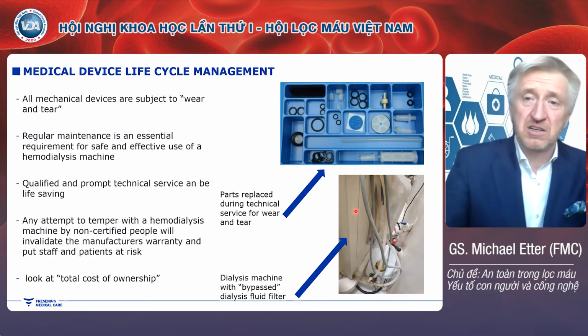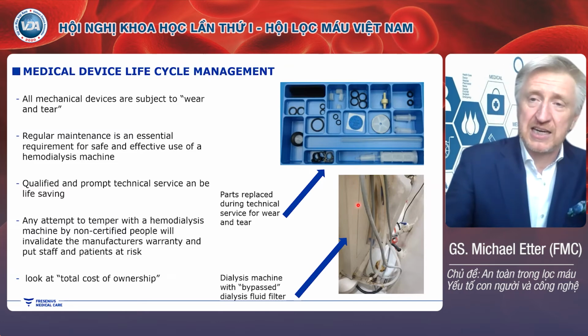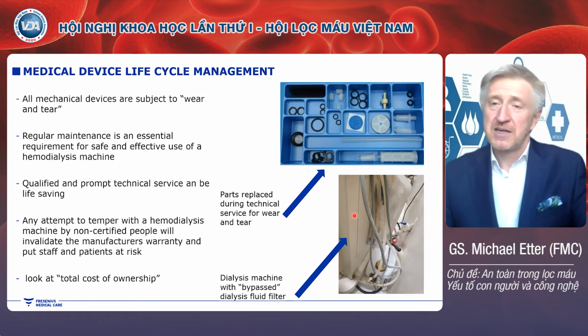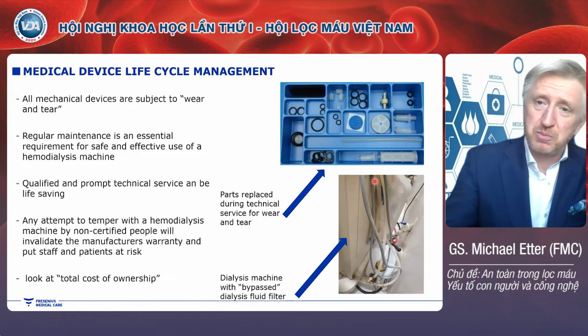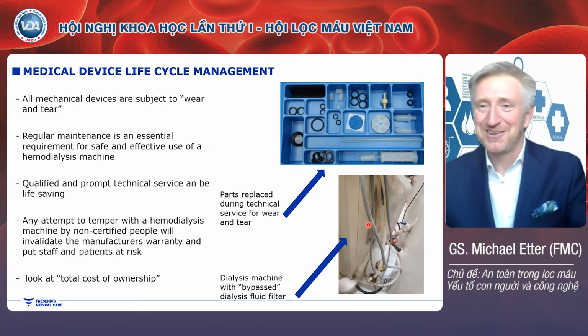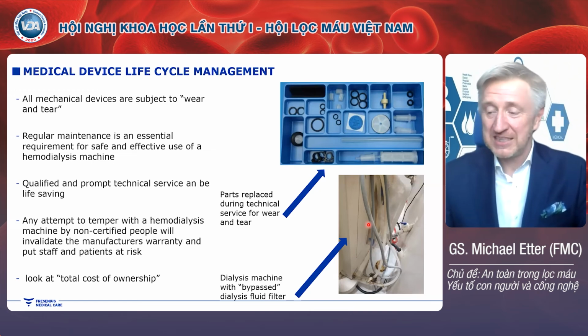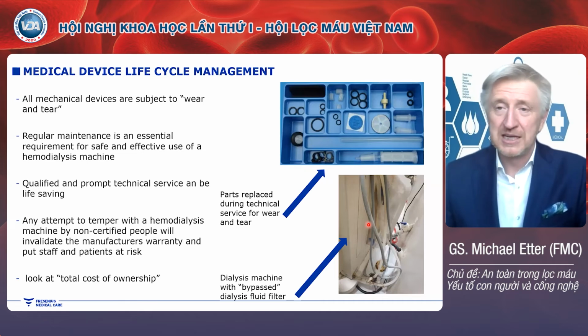Look at this picture here on the right-hand side. That's something I found in a dialysis unit, not in Vietnam, but also here in Asia, where in this area there should be a water filter. If you listened to the previous talk, you know exactly how this should work. This filter should make sure that the dialysate is ultra pure. But here, this water filter has been bypassed.